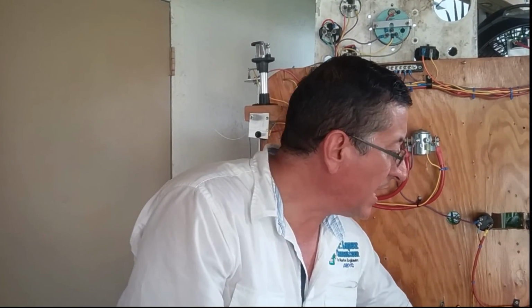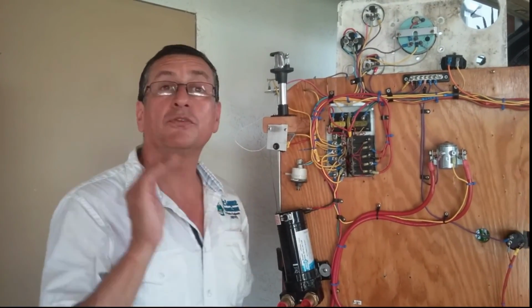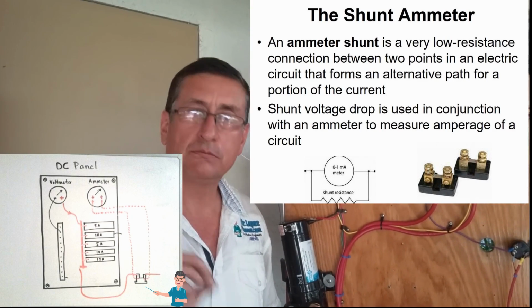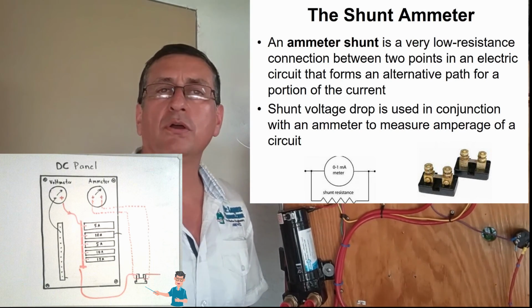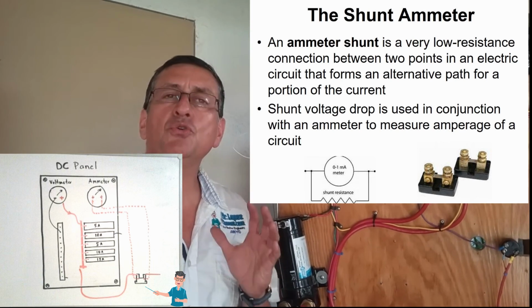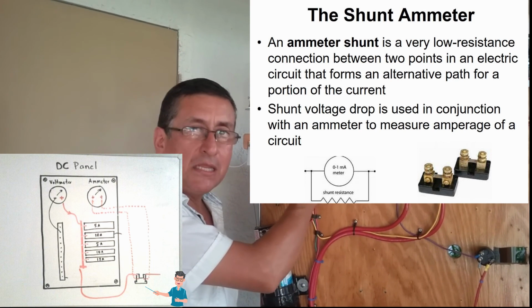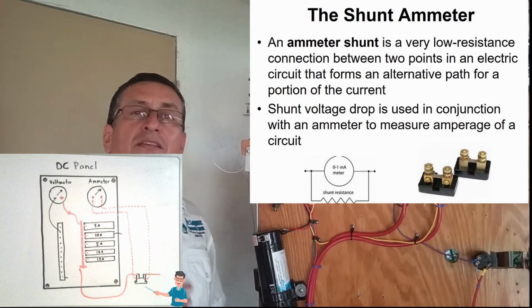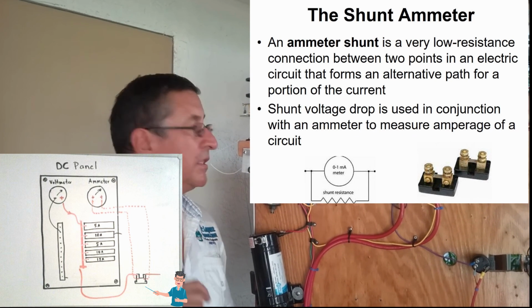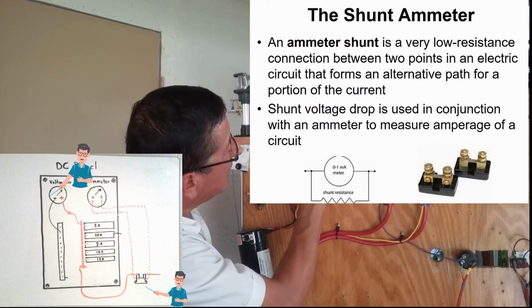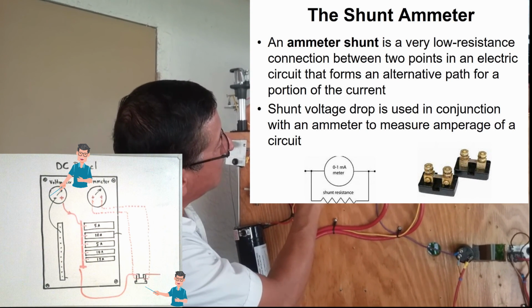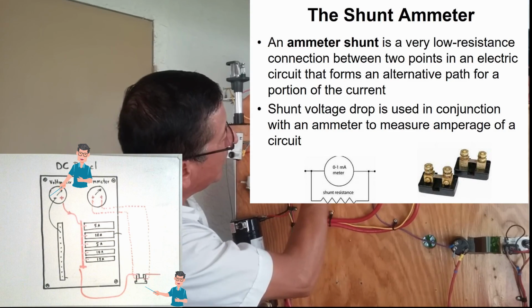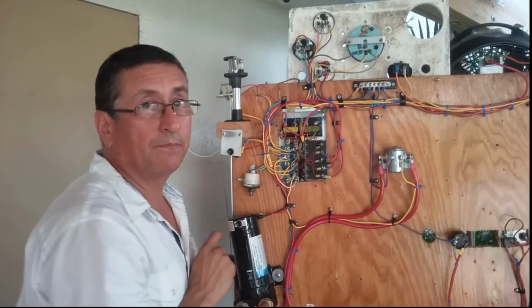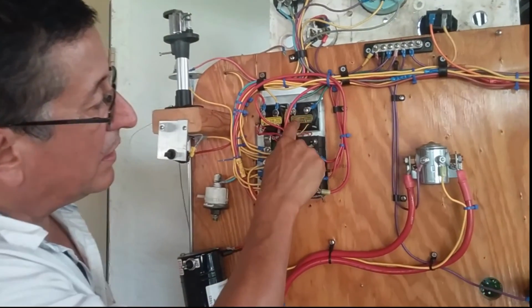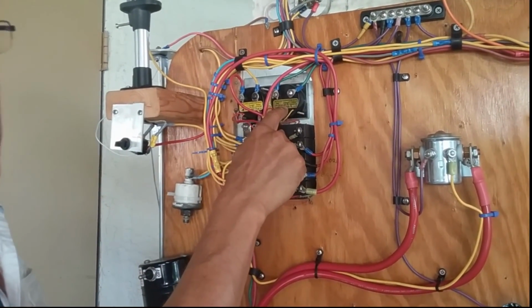When I use the ammeter of the panel, normally those ammeters for the small panels come with a shunt. The shunt that you have on the screen right now is like a resistor used to protect internally the winding of this ammeter. This is a resistor used to protect the ammeter. If you check, this ammeter has two terminals and both terminals of the ammeter are connected with a green cable, green and green, in order to connect the ammeter. If you check green and green, both terminals are connected here on the ammeter.